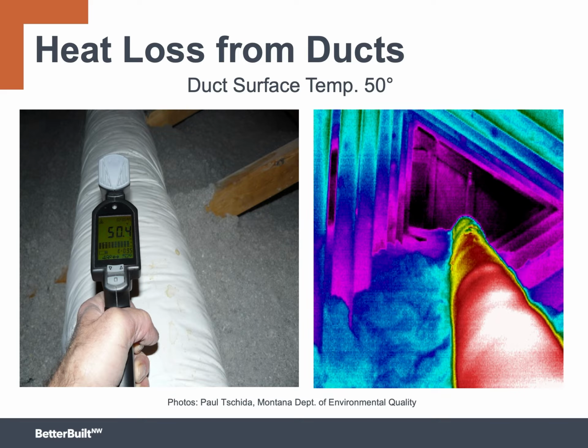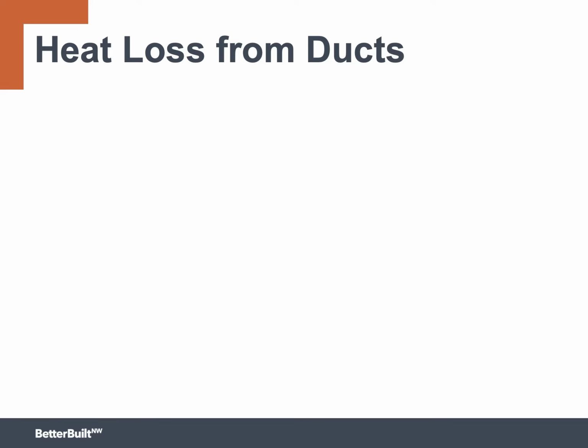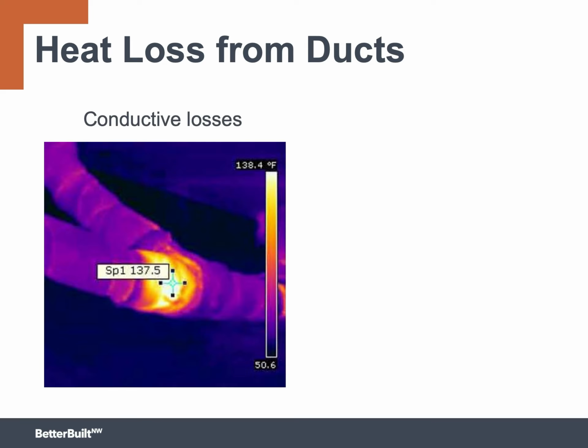That indicates that the duct is clearly warmer than the surrounding air, and you're really getting a lot of heat loss from the duct into the attic, even though the duct is insulated. This heat loss occurs in two different ways. First, you have conductive losses directly through the duct material itself. That's about half the heat loss.